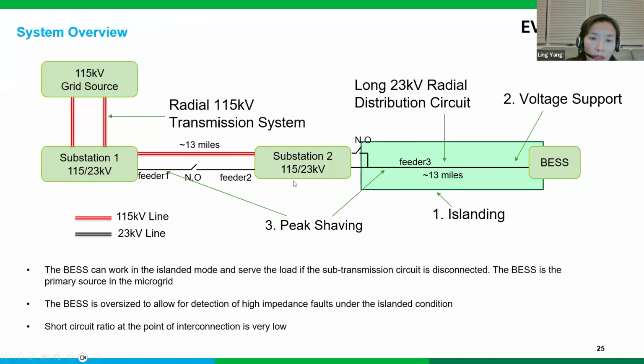The third one is that this substation is supplied by a radial 115 kV transmission line, and in case of these transmission contingencies, we are also going to use this battery to perform peak load shaving, because under these transmission contingencies, all the load of these 3 feeders will be picked up by feeder 1. So those are the primary use cases of the battery.